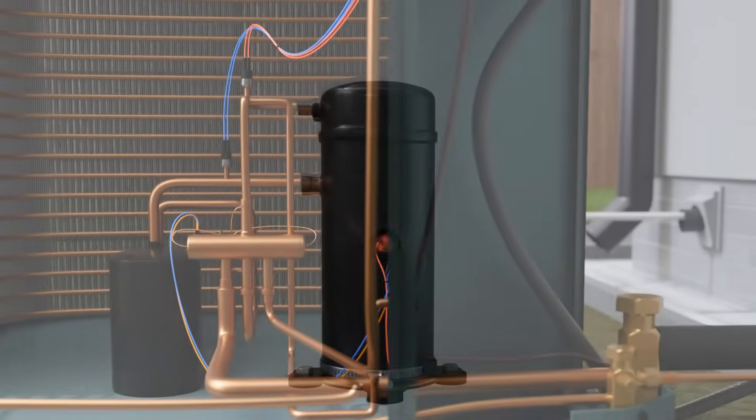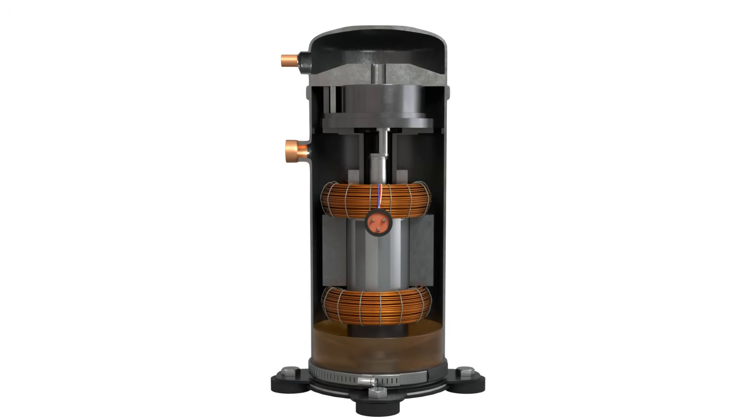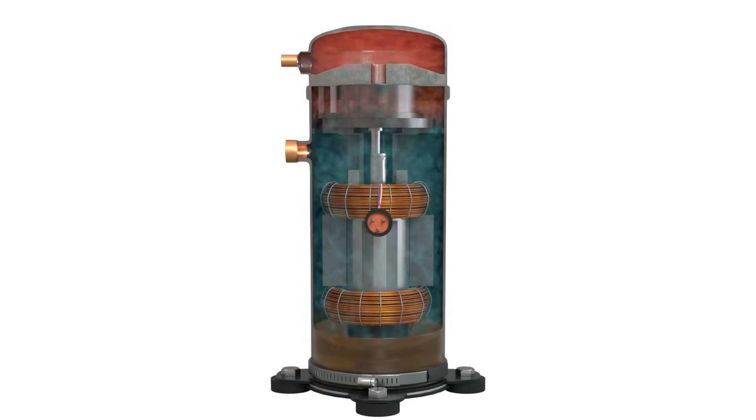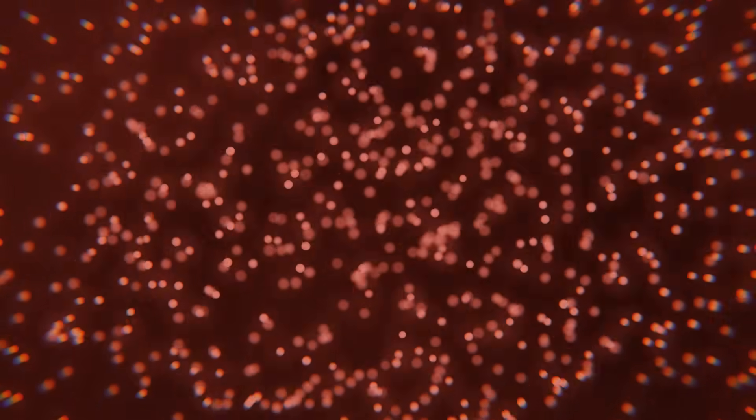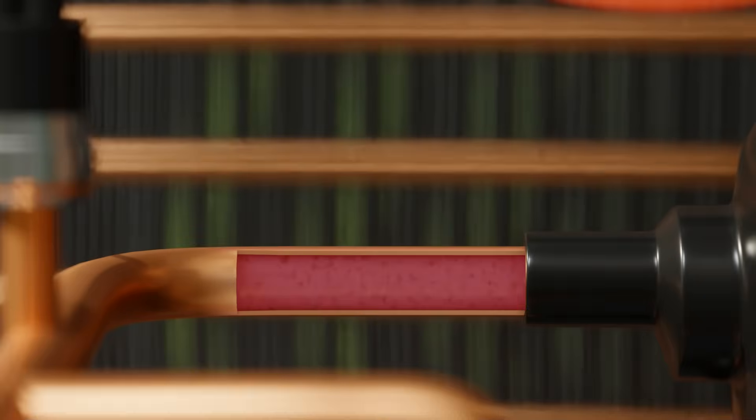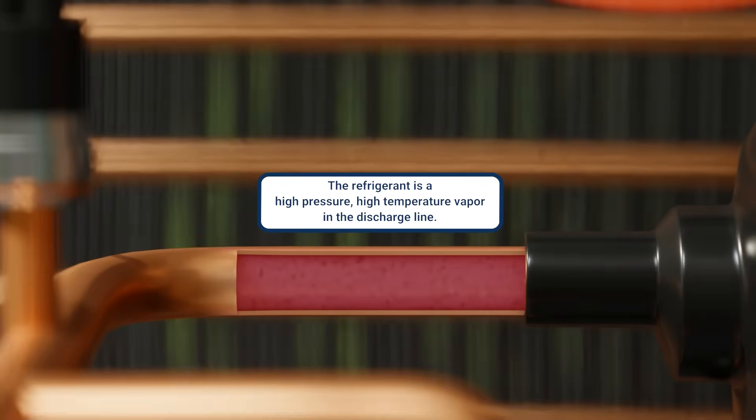Back to the compressor again. As the refrigerant enters the compressor, it is a cool vapor, and the molecules are moving pretty slow. Inside the compressor, the molecules of this cool gas get smashed together, so they move faster and get hotter. Remember, higher pressure equals higher temperature. When the refrigerant leaves the compressor, it's hot and under high pressure.